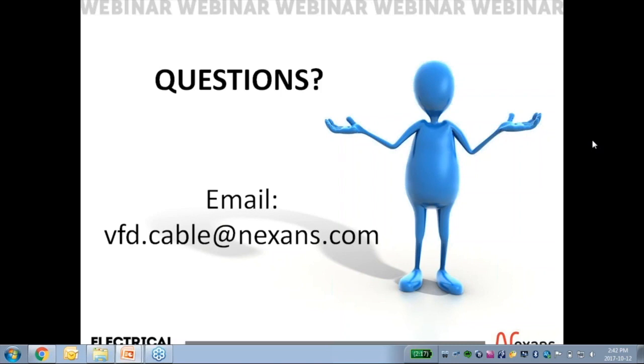Where that sheath or that conductive system surrounds all three cables in the grouping, or all the phase conductors, such as in a VFD cable, there's no need to account for that current or add a derating factor, so to speak. Again, that's been our experience with the cable so far. And there are no code requirements, to my knowledge, that dictate any need to add a correction factor or derating factor in the case of a multi-conductor cable under one common sheath.